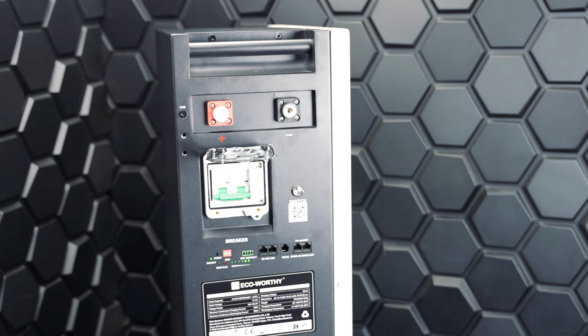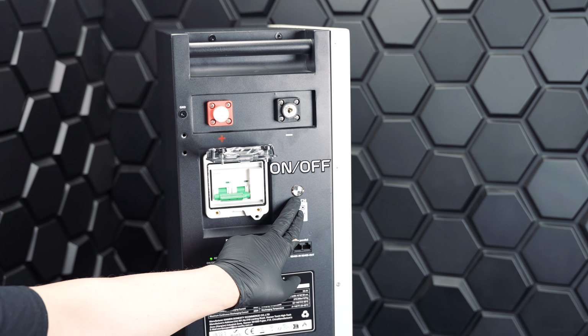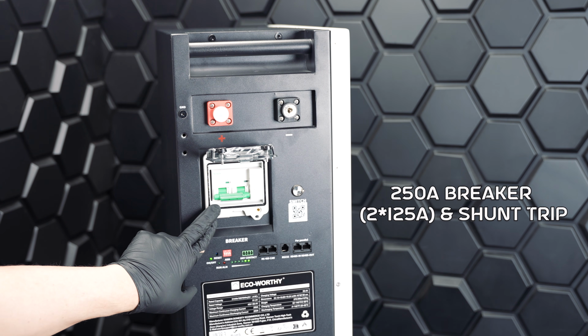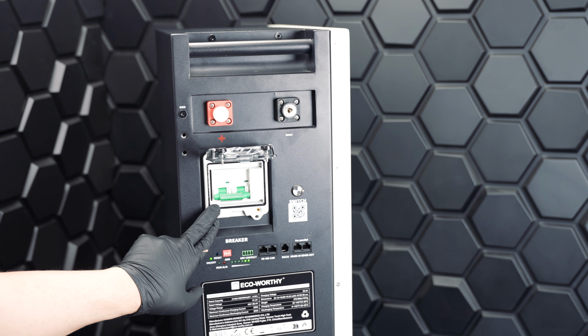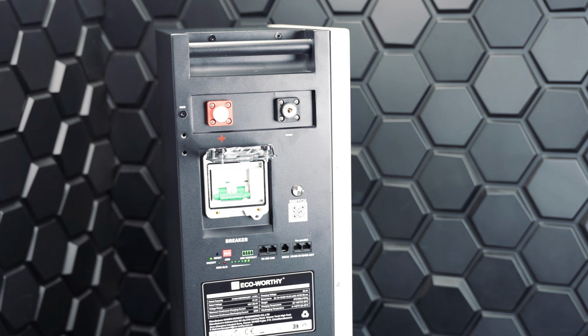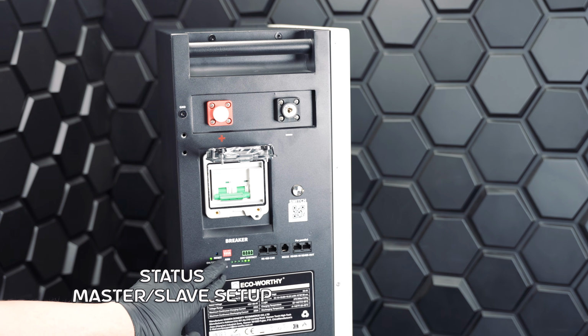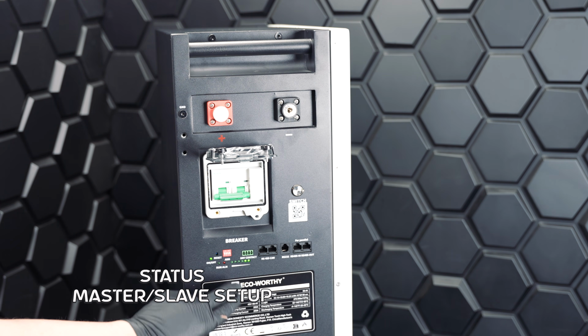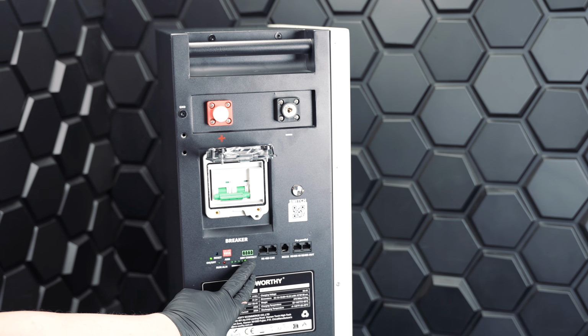Here's our very important on and off button. Then we have our 250 amp breaker and shunt trip for overcurrent protection and BMS second level protection. Then we have our status indicator lights as well as the add and dry contact switches to set up our battery as master or slave.